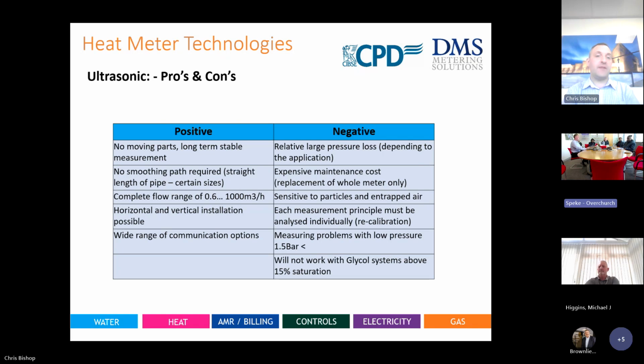Back to the smoothing paths: compared to the mechanical, they're a lot less required. I used to term it 3 pipe diameters before and after. That is your absolute minimum. So your design is a lot smaller, again saving some costs. The flow range covers 0.6 to 1,000 cubic meters, so they're quite sensitive to low flows on lower flow applications, and obviously in big district heating systems they're acceptable for high flows, and more or less everything in between.